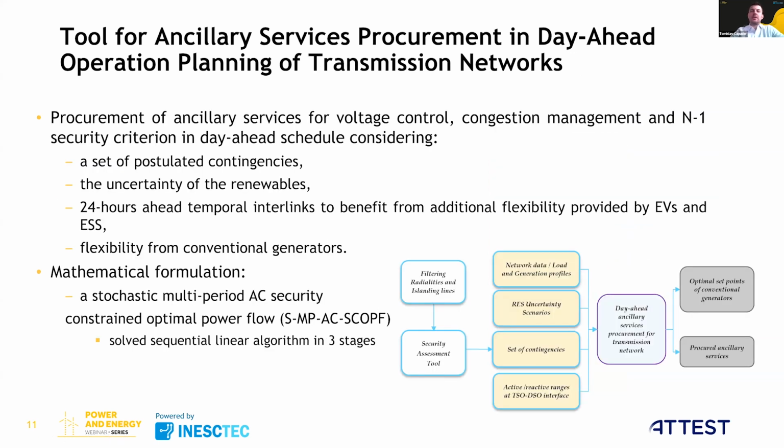At the transmission level, things are a bit more complex. As I said, we gave a priority to the transmission system operators when we designed the mechanism. So now we need to take into account a set of postulated contingencies. So we define the expected contingencies. Again, there are more renewables of a larger scale connected to the transmission network.